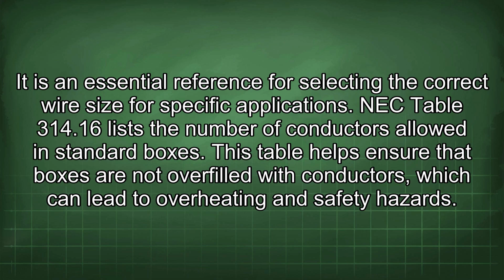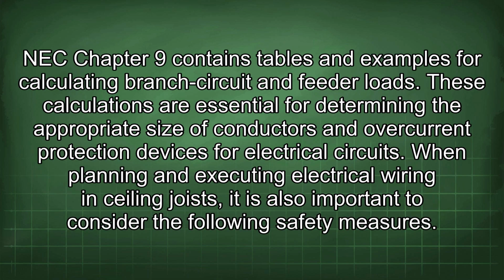NEC Table 314.16 lists the number of conductors allowed in standard boxes. This table helps ensure that boxes are not overfilled with conductors, which can lead to overheating and safety hazards. NEC Chapter 9 contains tables and examples for calculating branch circuits and feeder loads. These calculations are essential for determining the appropriate size of conductors and overcurrent protection devices for electrical circuits.